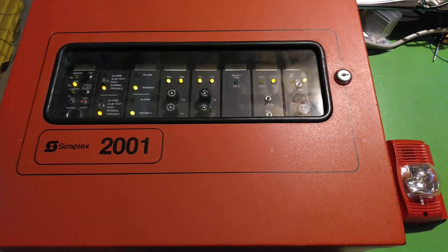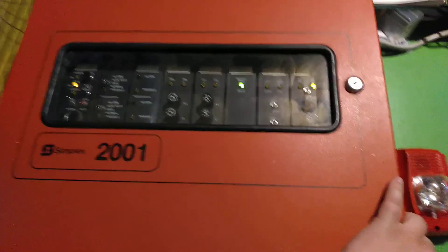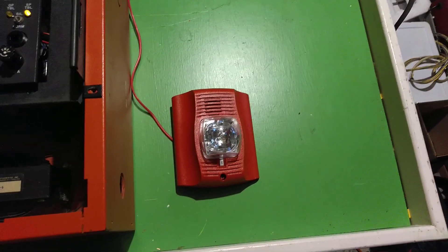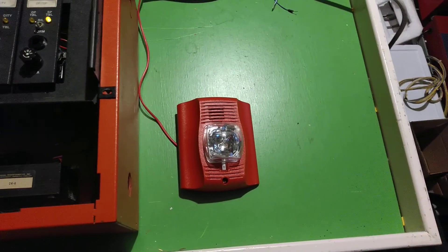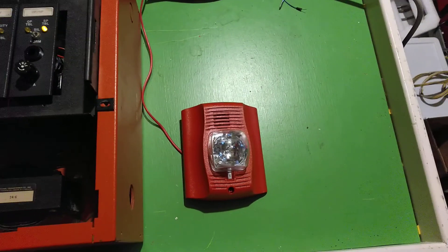Seems set up as last time. Left the March time card in there, but we won't really be using that today. We'll be using one NAC circuit, and it's going to be on steady and silenceable. I'm going to hit one of the test switches there, because I didn't take the time to wire up any initiating devices.